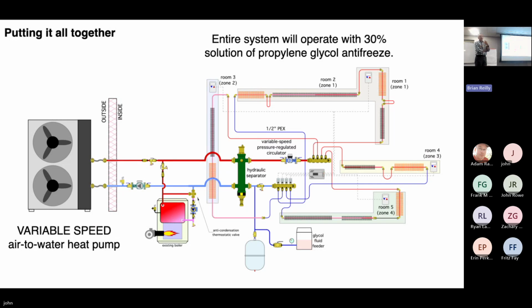And the heat pump could be set to maintain a certain outlet water temperature, like 50 degrees. And it'll just modulate. If you had 2 or 3 zones of cooling, and as those zones turn on and off, the heat pump will just, if it's a variable speed compressor, which many of the units are today, adjust the compressor speed to maintain that outlet chilled water temperature. So there are multiple possible solutions, but you've got to ask the questions up front.